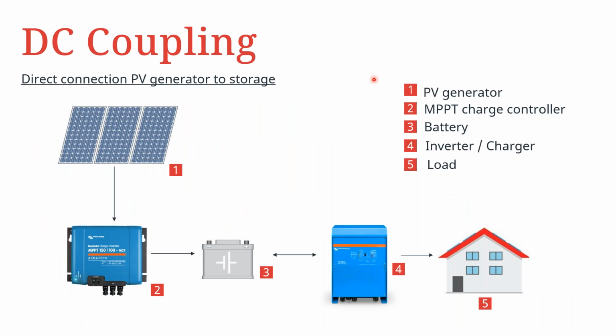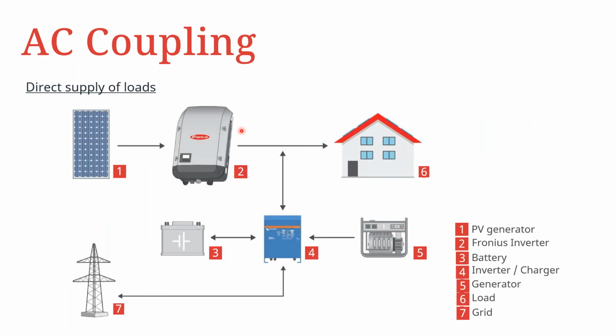So let's now get into the principle of AC coupling, and try to understand what this kind of system looks like. The typical setup for, let's say, off-grid applications would involve a DC coupled system. In this case, we are talking about the direct connection of a PV generator to a storage system. As you can see here, we have the PV array, the MPPT charger, the battery storage, and then the inverter charger, and eventually the load that is being supplied by this system.